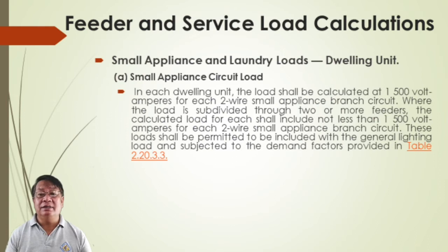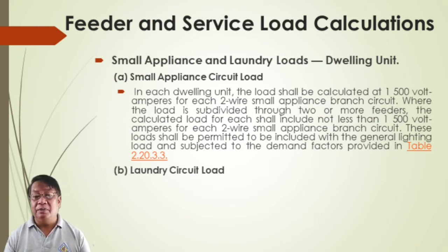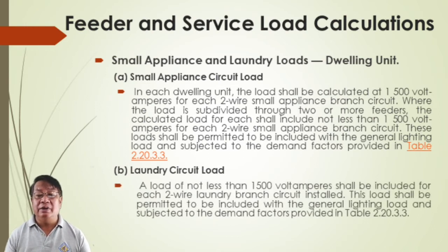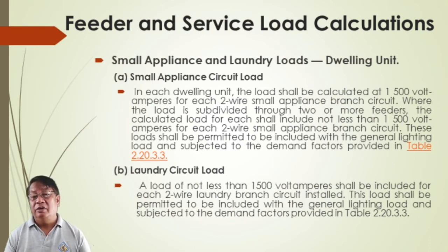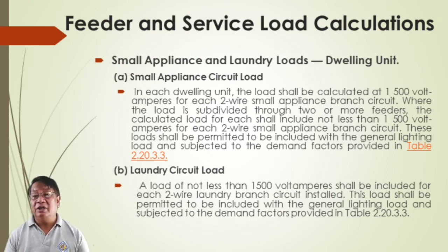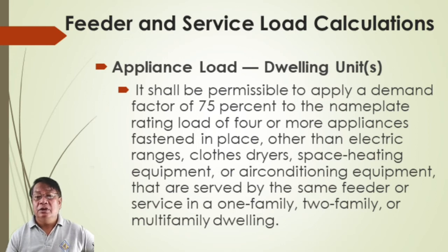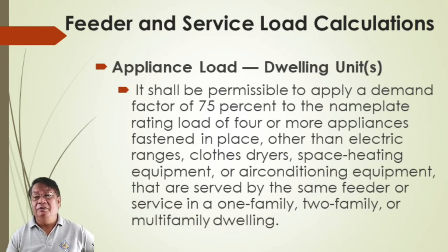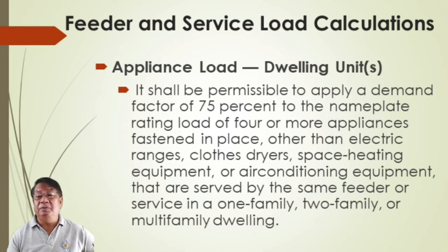For small appliance laundry, going back to Table 2.20.3.3, for the laundry circuit, try to allocate 1,500 volt-amperes for each two-wire laundry branch circuit. A demand factor of 75% shall be permitted to be applied for appliance loads of the nameplate rating for four or more appliances fastened in place, other than electric ranges, clothes dryers, and space heating — which have different demand factors.